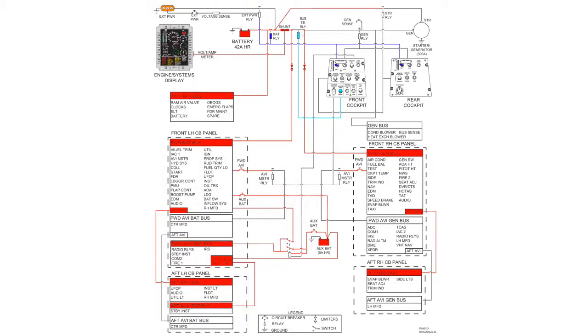Once the external power cable is connected and the source is turned on, power will flow down the line and hold at the external power relay. The power will also flow down to the voltage sensing circuit where it is checked for under or over voltage. Once it's verified, it will flow over to the external power relay where, combined with the signal from the battery switch, it will activate the relay.